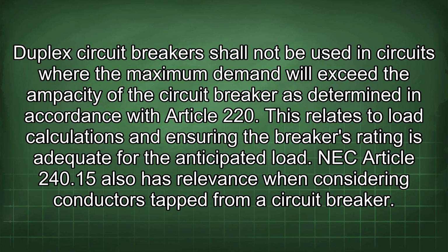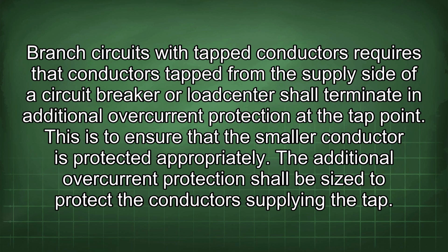NEC Article 240.15 also has relevance when considering conductors tapped from a circuit breaker. Branch circuits with tapped conductors require that conductors tapped from the supply side of a circuit breaker or load center shall terminate in an additional overcurrent protection at the tap point. This is to ensure that the smaller conductor is protected appropriately.